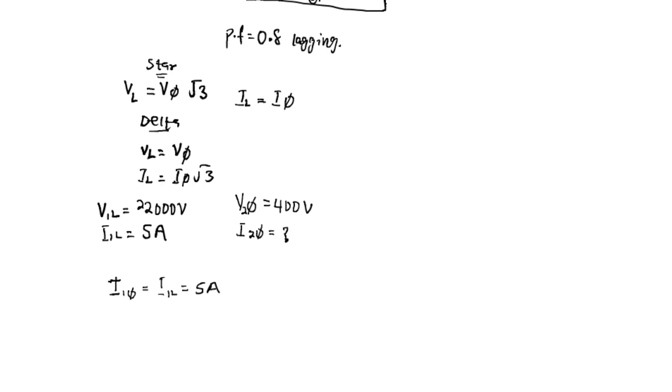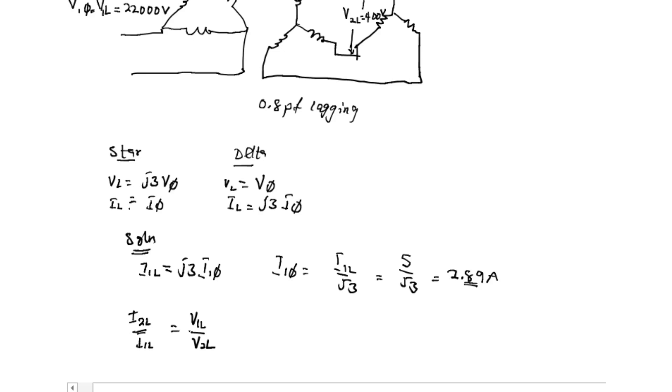To find the current of the secondary, we use the relation V1L × I1L equals V2L × I2L. Since the line current of the transformer on the secondary is the same as the phase current, it follows that I2L equals V1L divided by V2L times I1L. This is 5 times 22,000 divided by 400, which equals 275 amperes.